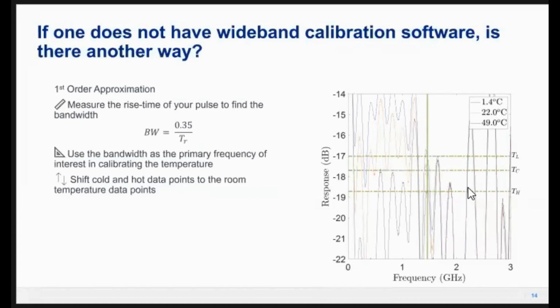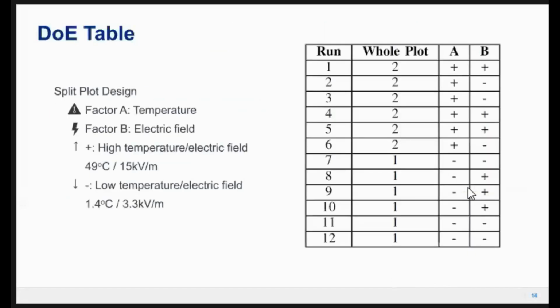Now, in terms of the calibration aspect, without using a specialized wideband software, in this case, we took the 10 to 90 rise time and then got the frequency off of that, which was 1.46 gigahertz. And then from there, we did an initial first approximation, taking the low temperature to the control and the high temperature to the control, which was not exactly good enough yet. So that's where the DOE process comes in.